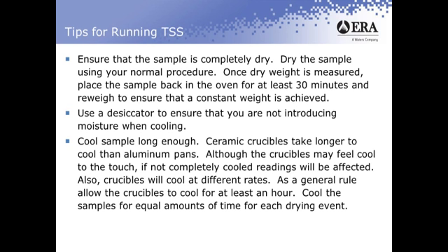Although the crucibles may feel cool to your touch, if they're not completely cooled on the inside of those walls, your readings will be affected. Also remember that those crucibles will cool at different rates. If you've got 10 of them, they're not going to completely cool at the same rate because they have slightly different thicknesses. As a general rule, I have found I would allow those crucibles to cool for at least an hour, and generally within an hour all the crucibles have fully cooled.